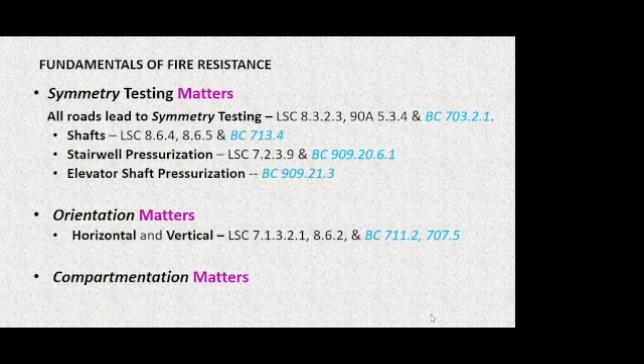And we're going to talk about some concepts that are fundamental fire resistance concepts that aren't often commonly discussed. If you're doing mechanical inspections or mechanical plans review, you're not necessarily playing around in chapter 7 of the building code too much. And yet that's where most of this criteria is going to come to play. And it's really important to recognize that it is so much more than just, well, we'll just put in a SMACNA-based ventilation system according to the mechanical code, and there's some things we might need to do to it. Nothing could be further from the truth once we get into the weeds. And we're going to get fairly deep into the weeds, because that's what it takes to get a true understanding of these issues.